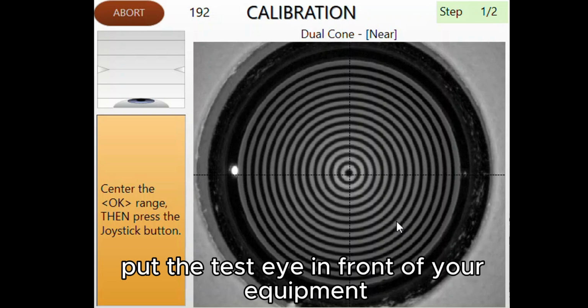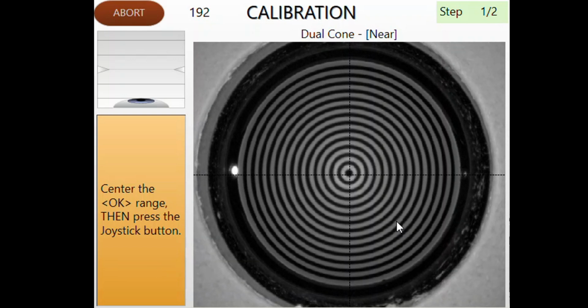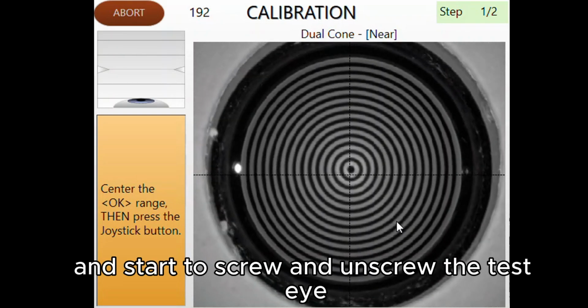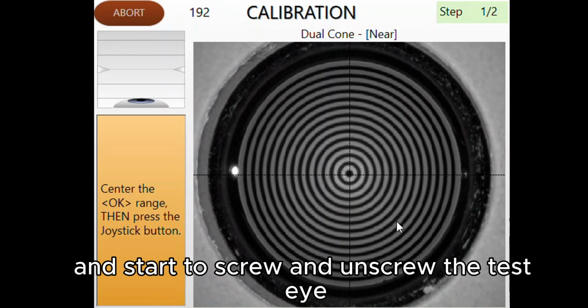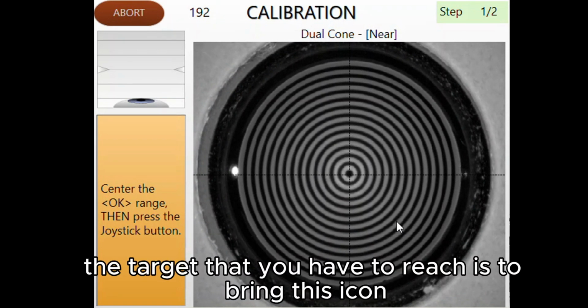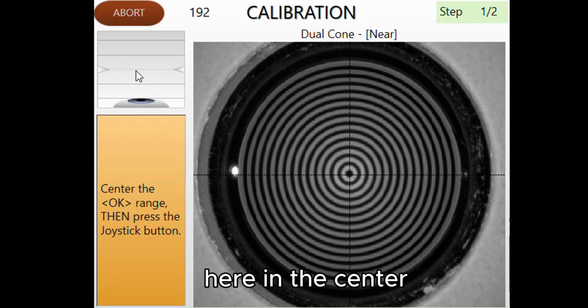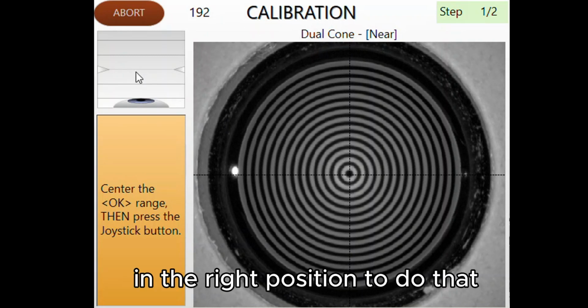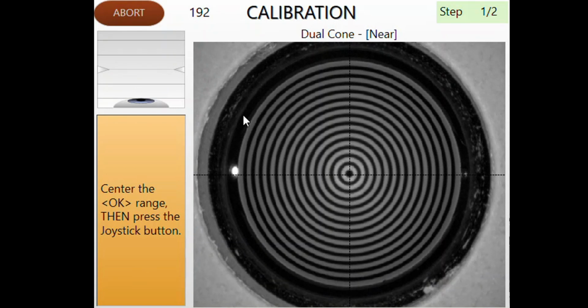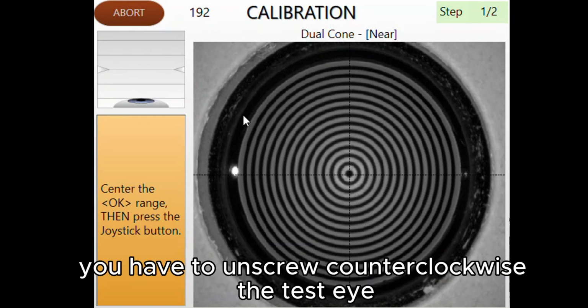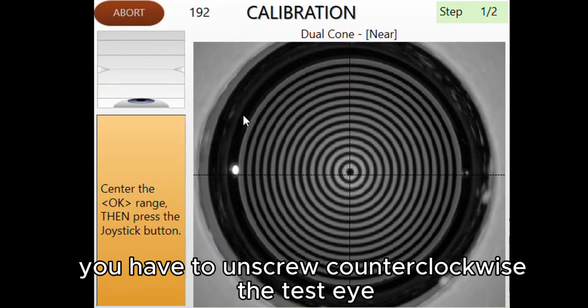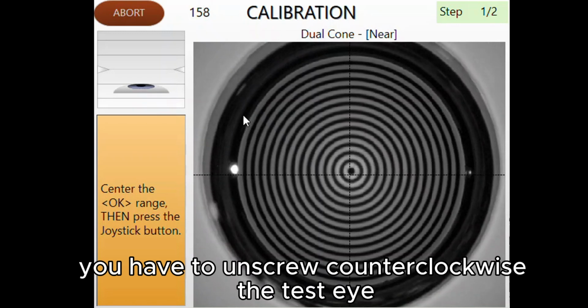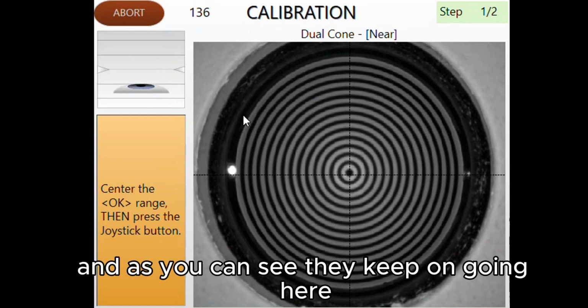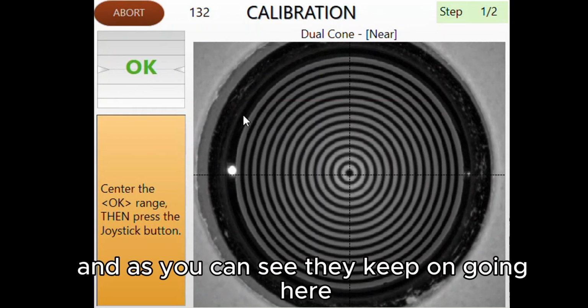Put the test eye in front of your equipment and start to screw and unscrew the test eye. The target that you have to reach is to bring this icon here in the center, in the right position. To do that, in this situation, you have to unscrew counterclockwise the test eye. And as you can see, the equipment goes near.